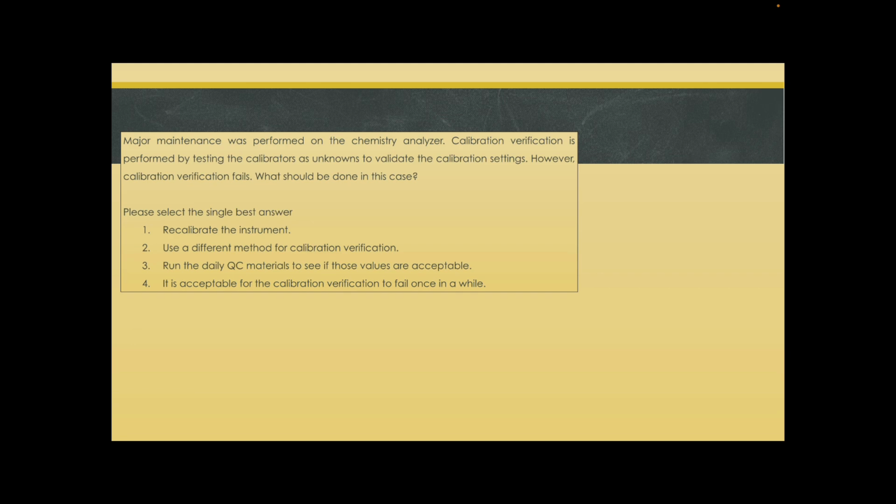1. Recalibrate the instrument. 2. Use a different method for calibration verification. 3. Run the daily QC materials to see if those values are acceptable. 4. It is acceptable for the calibration verification to fail once in a while.